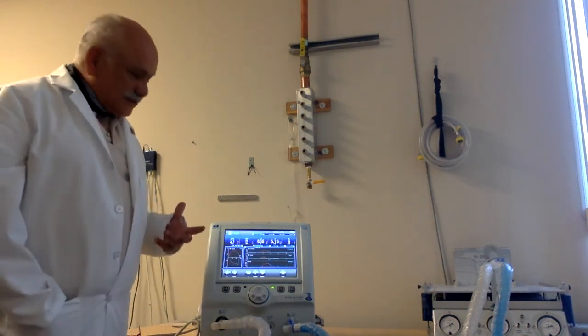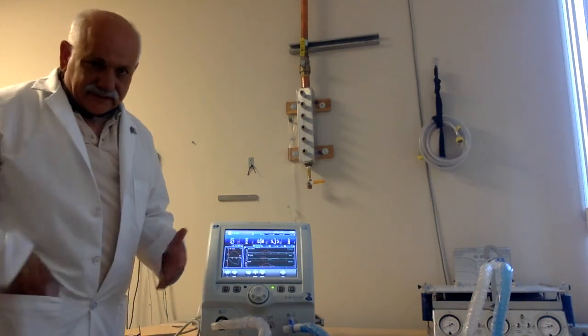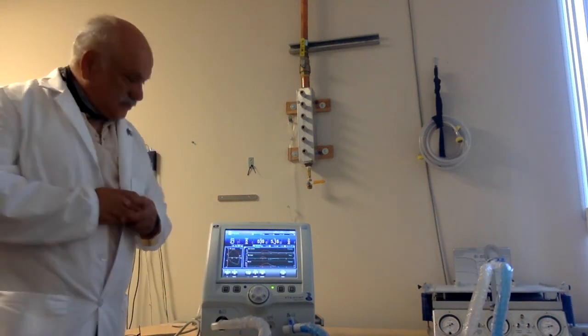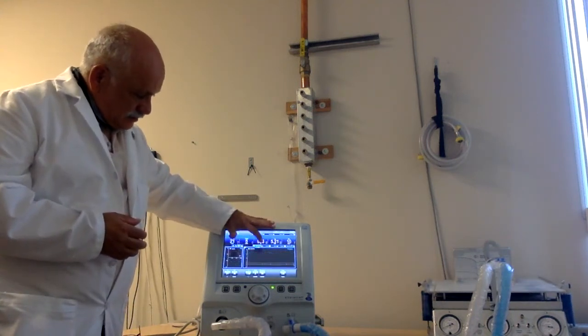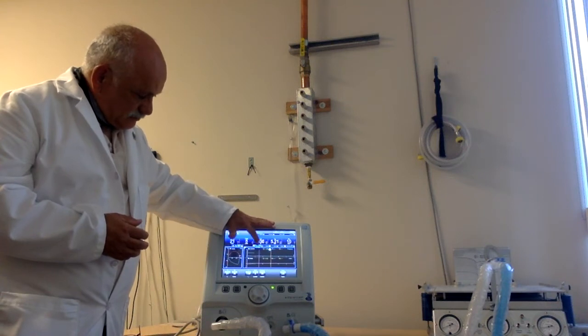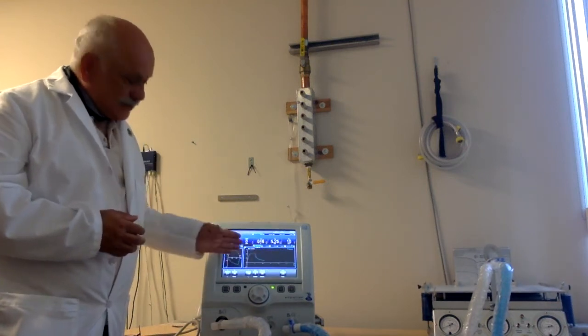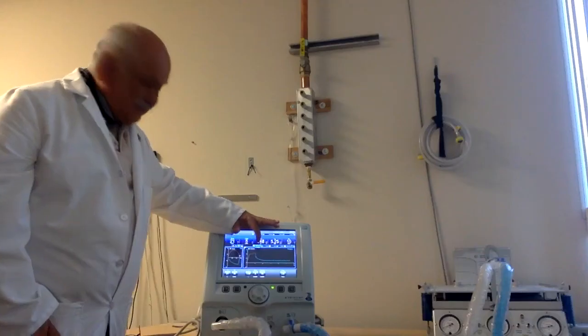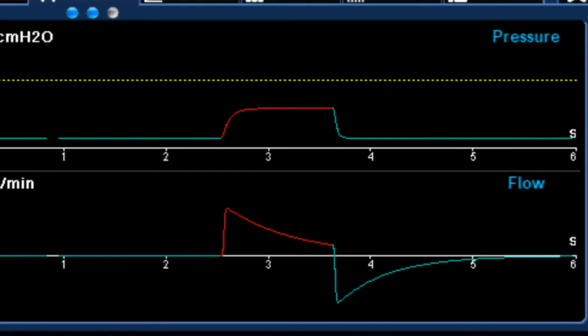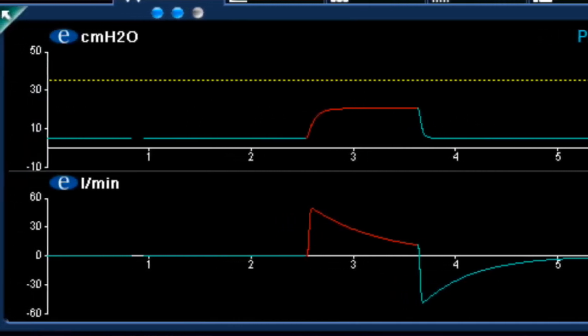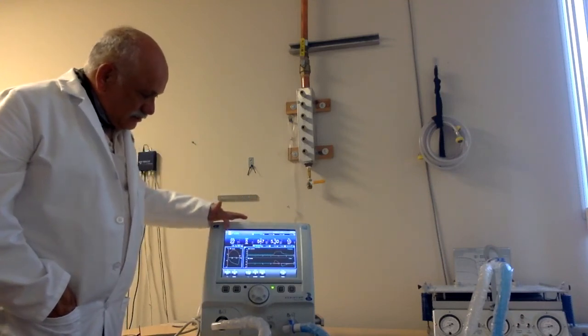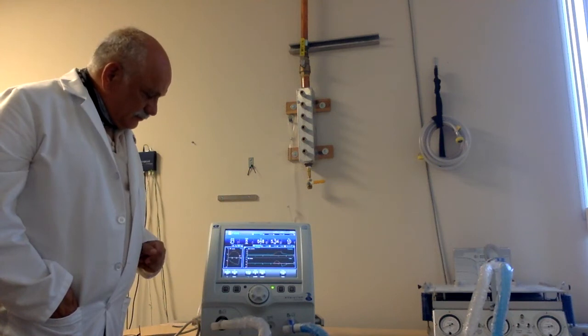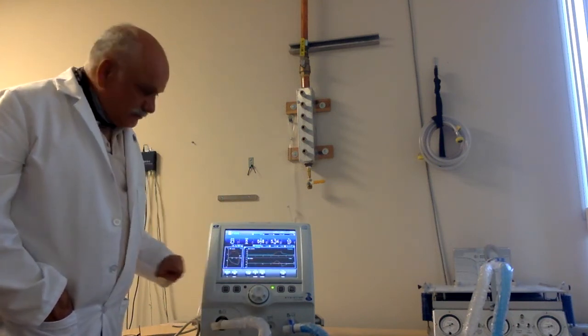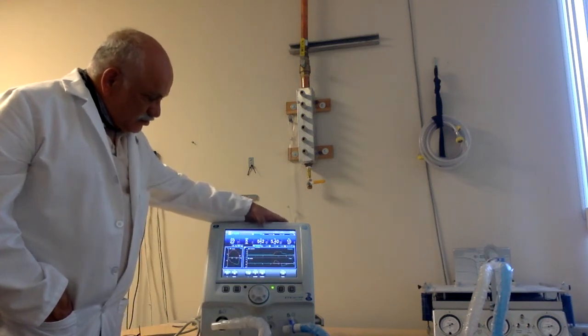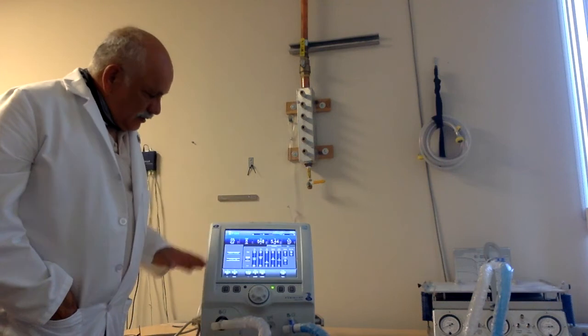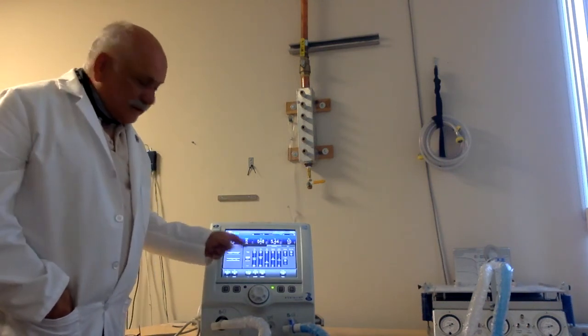Now sometimes I want to see these waveforms in a different way. I want to see them larger. I may pick my two favorite waveforms. This ventilator allows you to easily choose between waveforms. Here's a single waveform, pressure over time, but I'm a fan of pressure over time and flow over time. So here we are. Again, digital parameters, what's going on with the patient's breathing, what's the patient's settings, and should any alarms occur, I'm able to get started immediately by looking at the alarm screen.